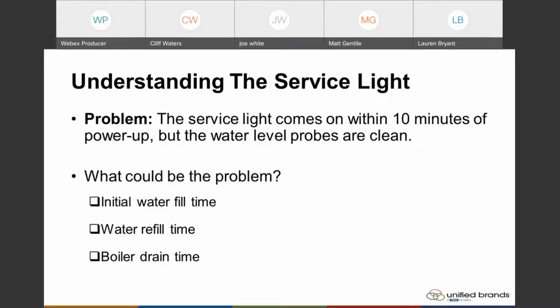The service light comes on within 10 minutes of power up, but the water level probes are clean. So this is saying, hey, Joe said I need to clean this thing when the service light comes on, and I did that. Now what? Well, the problem could be the initial water fill time. Well, what creates a water fill time problem? It could be your water refill time. What creates that problem? Or it could be the boiler drain time.